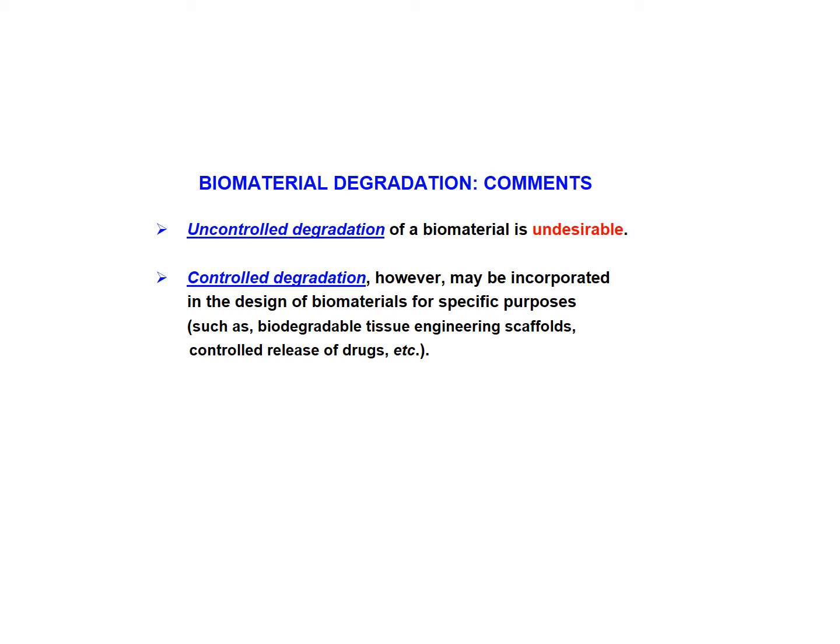The pertinent prerequisite tests also include in vitro material-related tests. A very important aspect which must be carefully considered and tested is that of the degradation potential of biomaterials in the physiological environment. Uncontrolled degradation, especially following implantation, is undesirable and should be avoided. However, in some cases, controlled degradation of a material is incorporated in the design for a specific purpose.